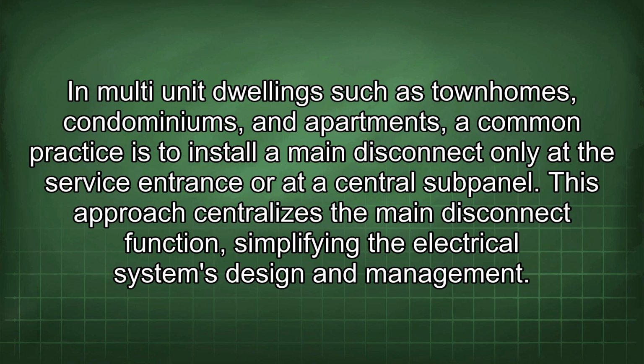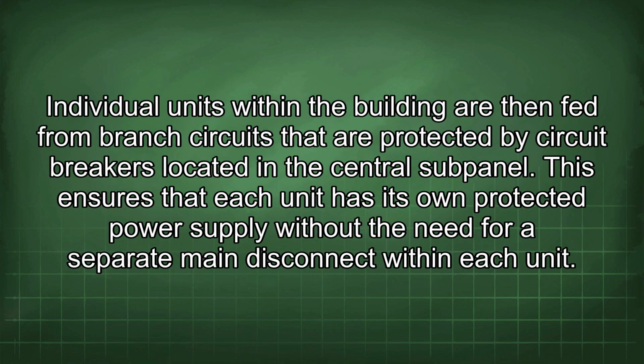In multi-unit dwellings such as townhomes, condominiums, and apartments, a common practice is to install a main disconnect only at the service entrance or at a central subpanel. This approach centralizes the main disconnect function, simplifying the electrical system's design and management. Individual units within the building are then fed from branch circuits that are protected by circuit breakers located in the central subpanel.